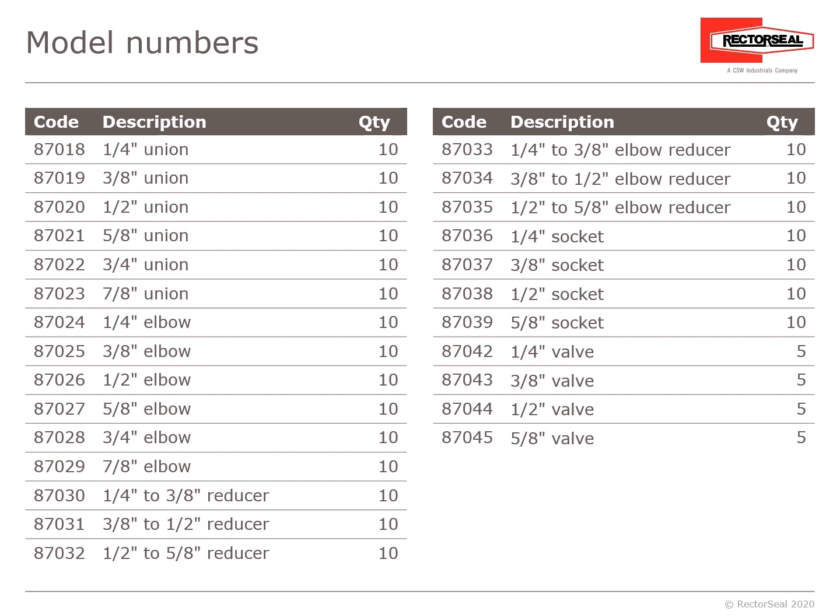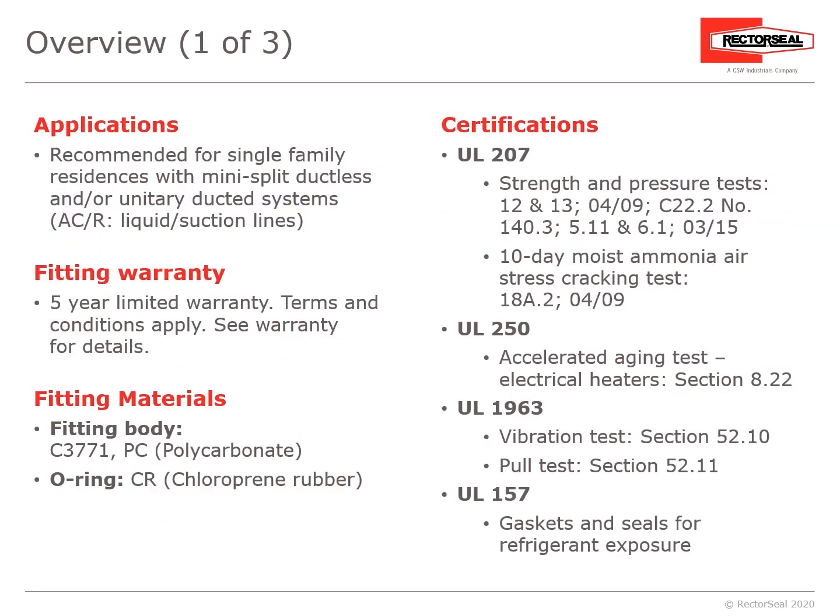We have the ¼-inch through ⅞-inch 90-degree elbow, ¼-inch through ⅝-inch reducer, a 90-degree elbow reducer, the ¼-inch socket for flare, and ¼-inch access valves. The ProFit Quick Connect is recommended for single-family residences with ductless mini-splits or unitary ducted systems. The warranty on the fittings is a five-year limited warranty. The fitting body is a polycarbonate brass body; the O-ring is a chloroprene rubber elastomer, making it impervious to leakage or breakdown when exposed to POE oil and refrigerants.